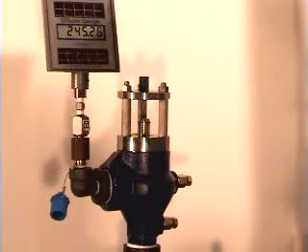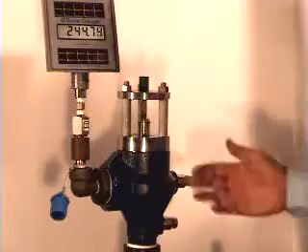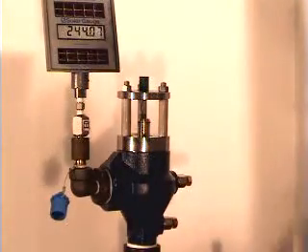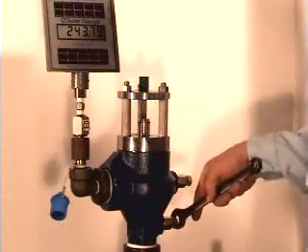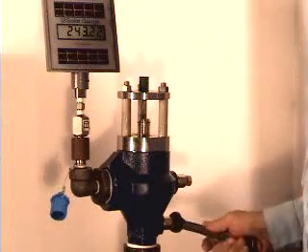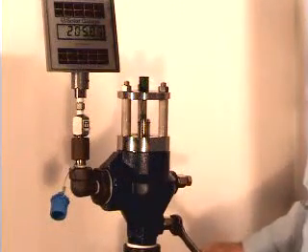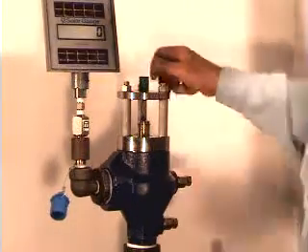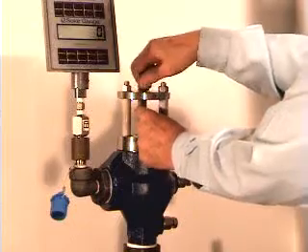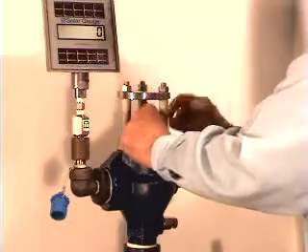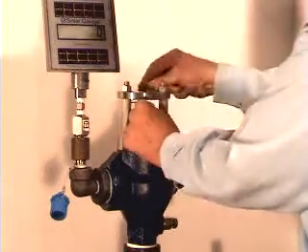In order to change the pin, I have to isolate this valve, shut off the pressure, bleed the pressure off of the valve itself, and then change it by taking off the adjusting or holding nut and pushing the piston to an open condition.